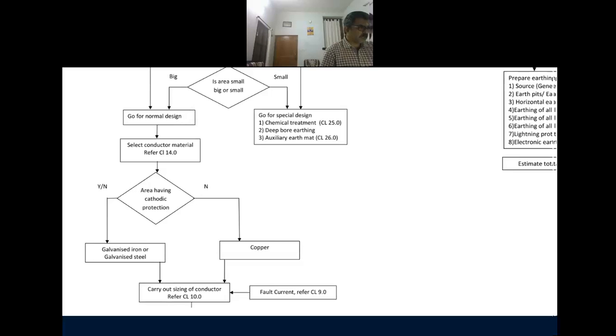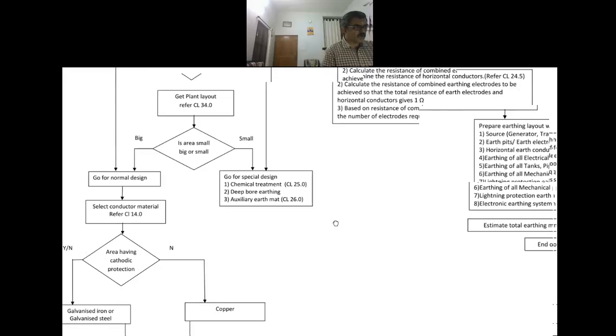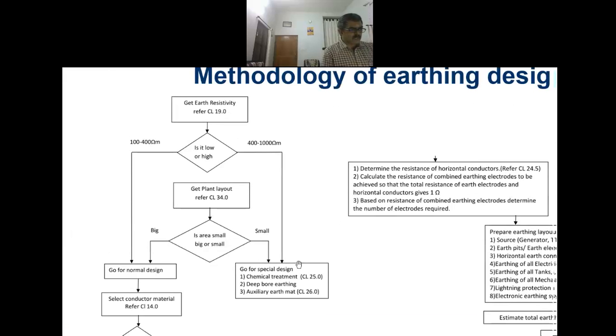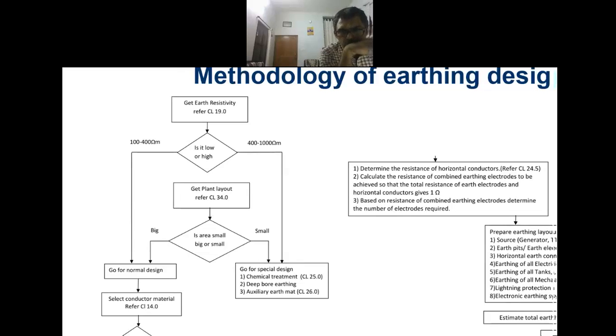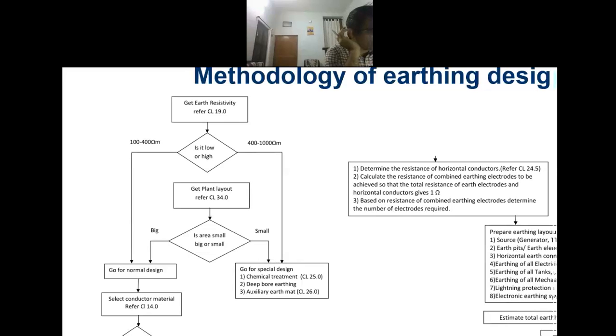Next, I have to size my earthing conductor, and for that I have to get the fault current. Now there is something called a chemical treated earth pit. In case the resistance is very high, there are some chemicals which can be added to the earth pit to reduce the resistivity. Later on I will tell you how and why that works.